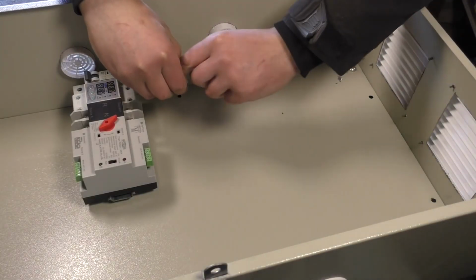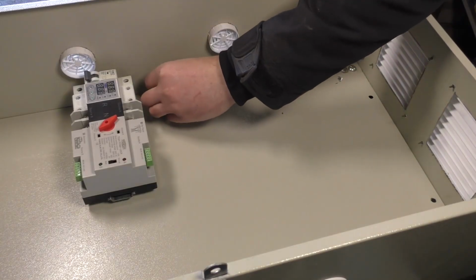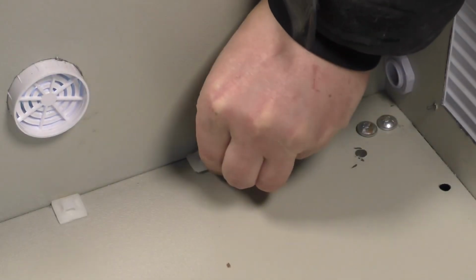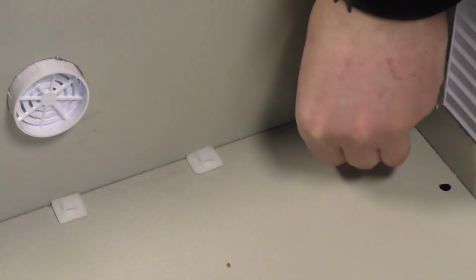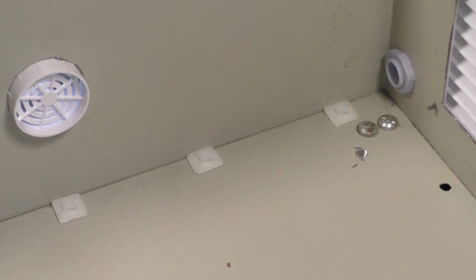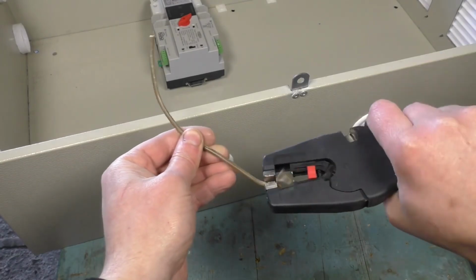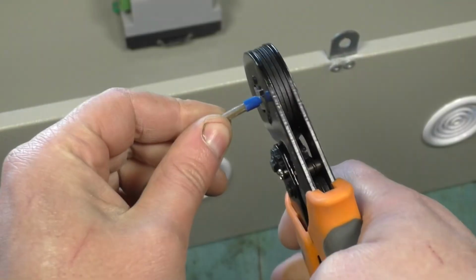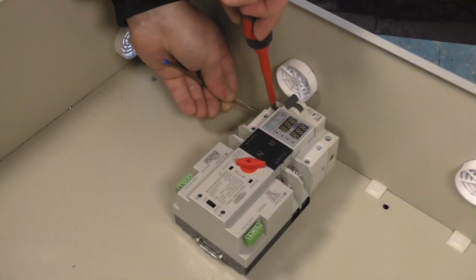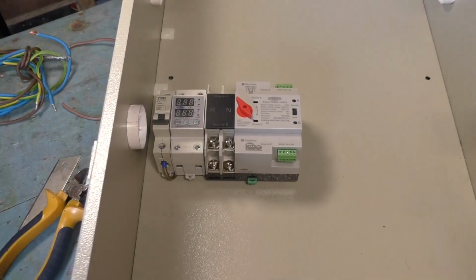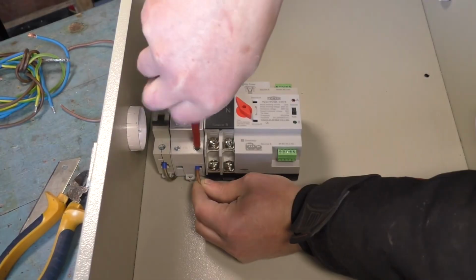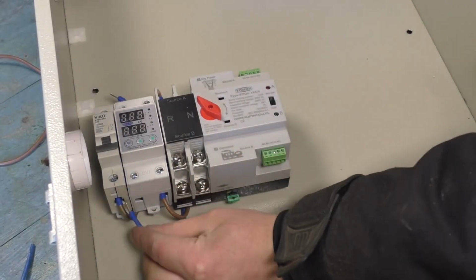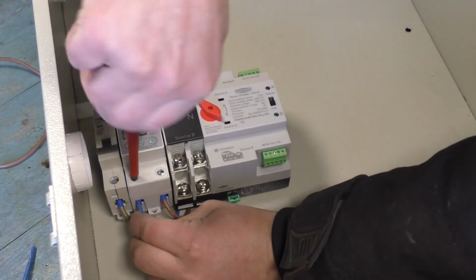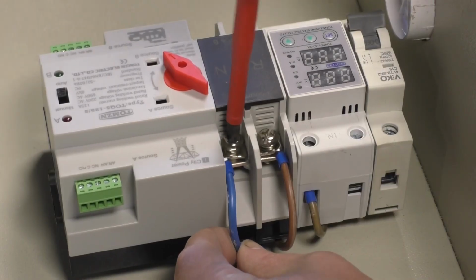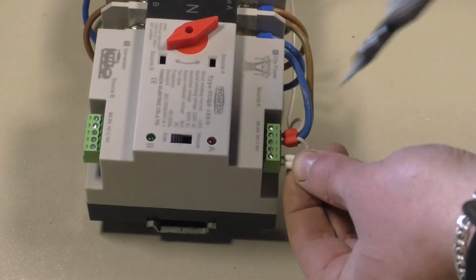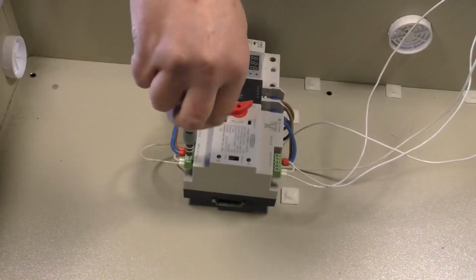We install the pads to which the cable will be attached. They are attached using double-sided tape, which can be bought at an electrical goods store. Next, we take pieces of wire, strip the insulation from them, and be sure to crimp them with ferrules. Now we attach these wires to all the modules. The wires are connected in advance because once all the equipment is installed, it will be inconvenient to work with these modules. And you will see the wiring diagram for all the equipment that will be installed in this panel a bit later, roughly at the end of the video.